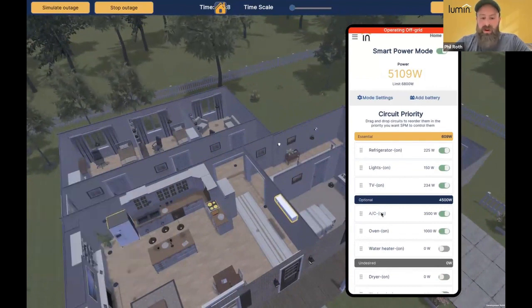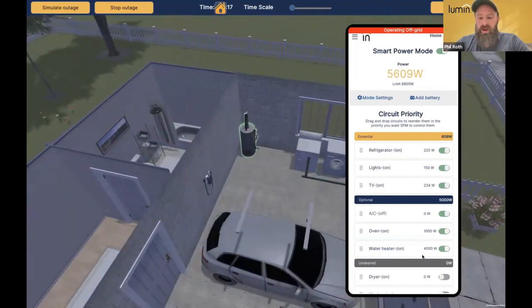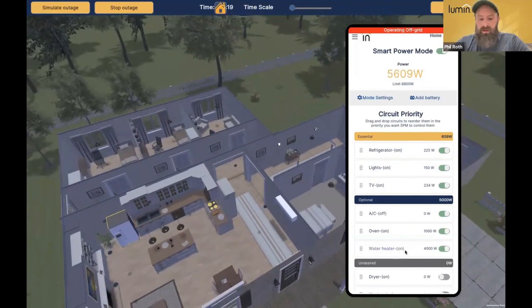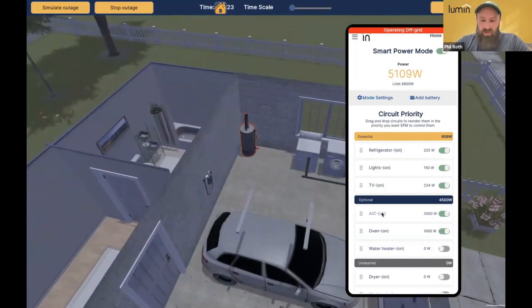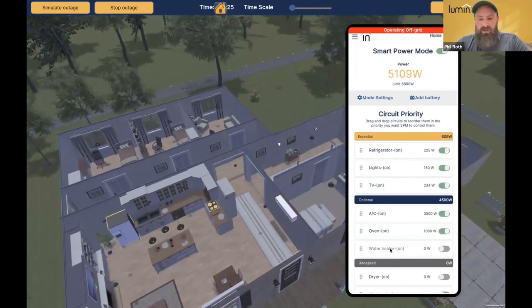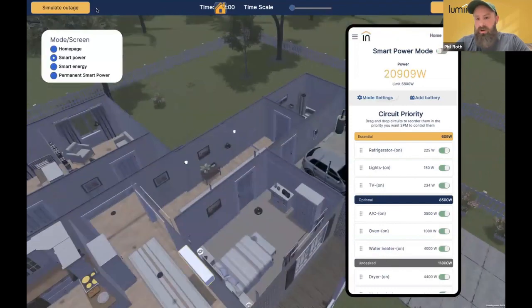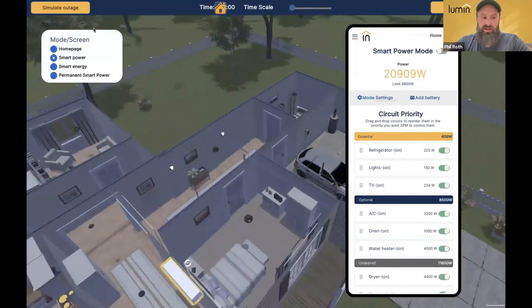As soon as one of our heavy optional loads finishes a cycle, say the AC gets to its thermostat setting, that's going to open up available capacity for the lower prioritized load. If a higher prioritized load starts using energy again, that's okay, it's going to turn off the lower prioritized load. As soon as the power outage is over, everything comes back just like it was.